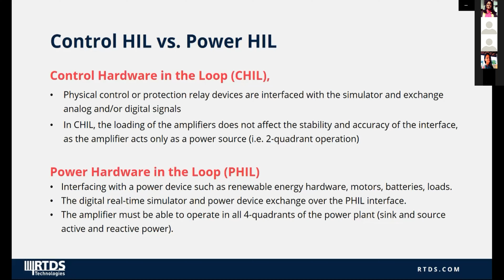Power hardware in the loop simulations involve interfacing the digital real-time simulator with a power device such as renewable energy hardware, motors, batteries, or load. Unlike control hardware in the loop, the digital real-time simulator and the external device exchange power over the power hardware in the loop interface. For closed-loop power hardware in the loop simulations, the amplifier must be able to operate in all 4 quadrants of the power plane, as it must be able to sink and source active and reactive power.